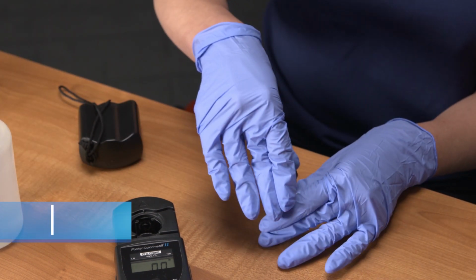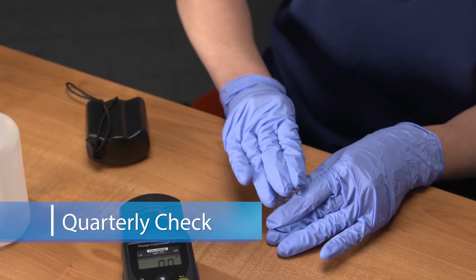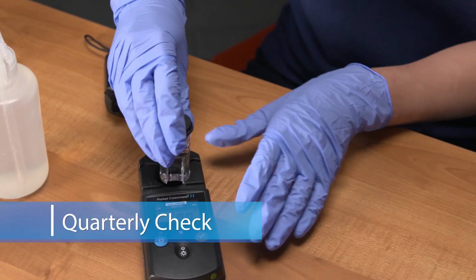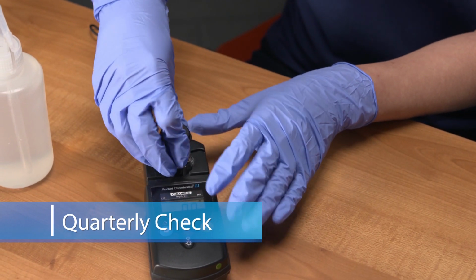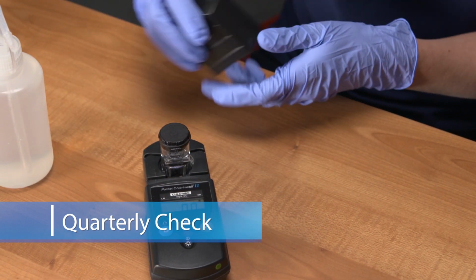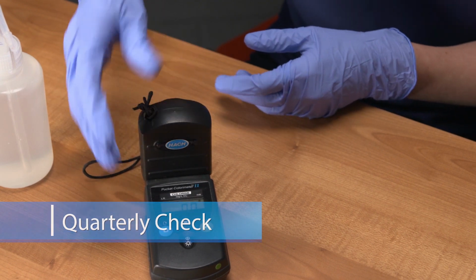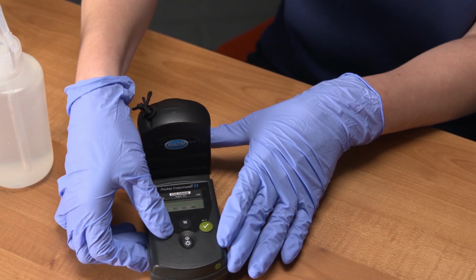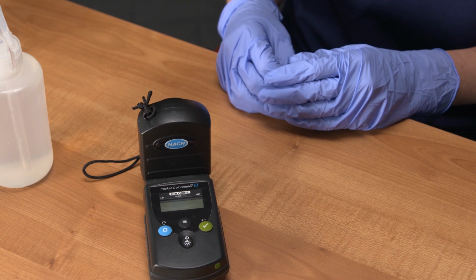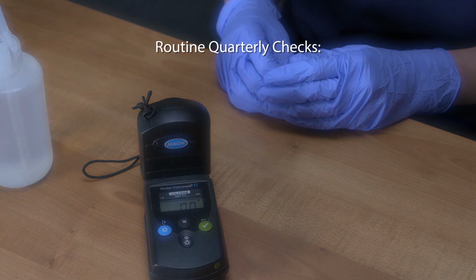Routine quarterly checks. Most of the time, we will be performing quarterly checks. Quarterly calibration verification checks are needed to make sure the instrument, glassware, and reagents are still providing accurate results. A quarterly check consists of 3 quality assurance procedures. First, a quarterly check begins with a method blank measurement. The procedure for performing a method blank can be viewed again, as this was discussed previously.